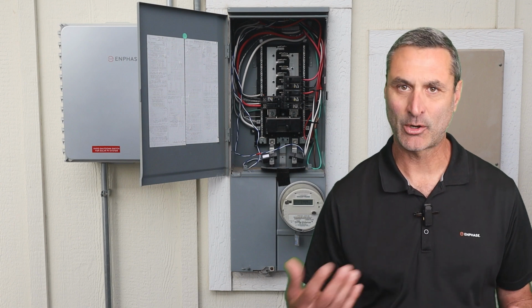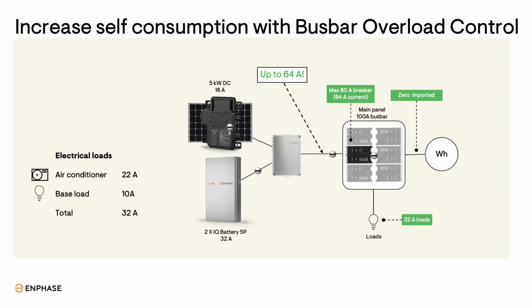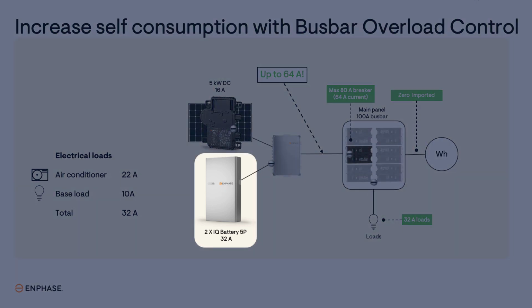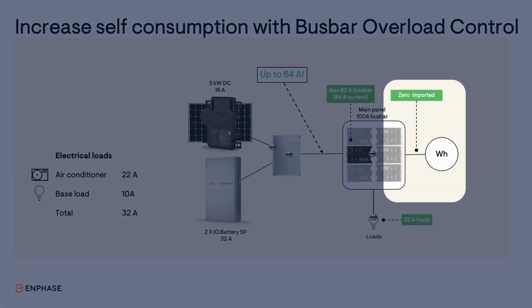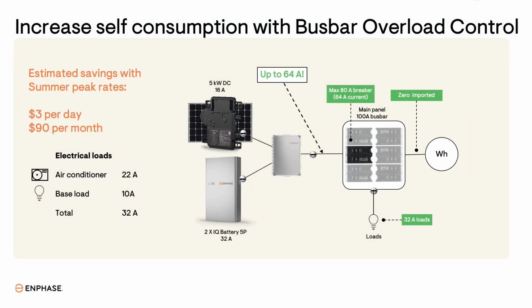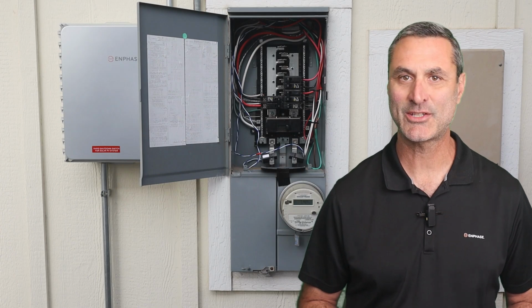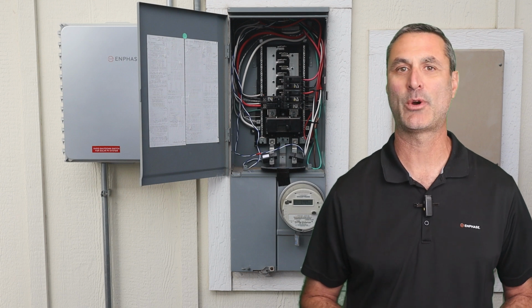Now, with busbar overload control, the solar and battery system will be allowed to discharge at their maximum power, which would be over 32 amps with two Enphase IQ Battery 5Ps, plus what the solar is producing. And the home would draw zero expensive power from the grid. Self-consuming more solar energy and reducing use of grid power would save the homeowner $3 per day or $90 per month in this example. The second real-world benefit applies to homeowners in California with NEM 3.0.